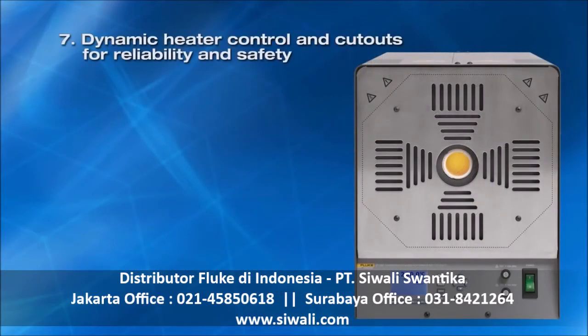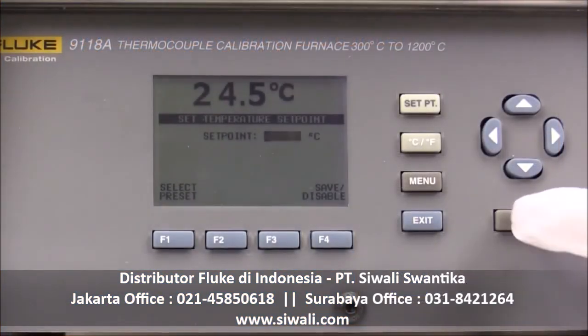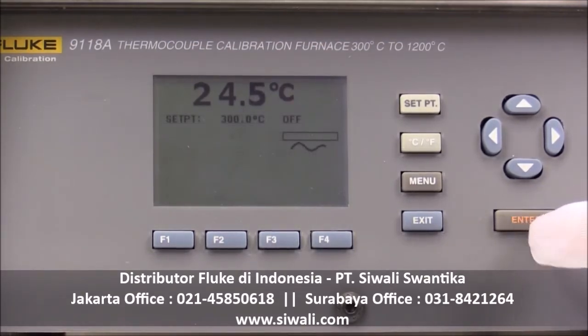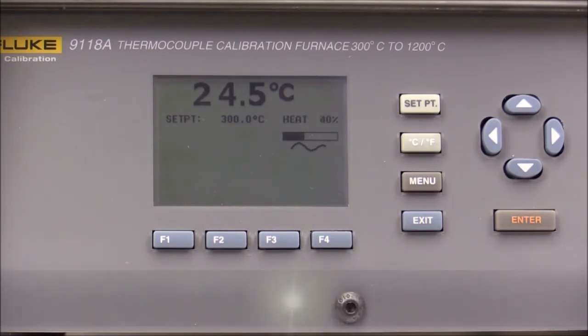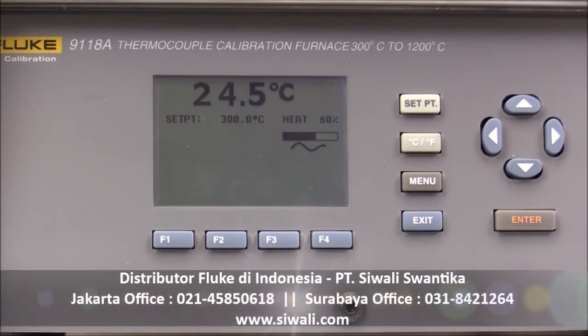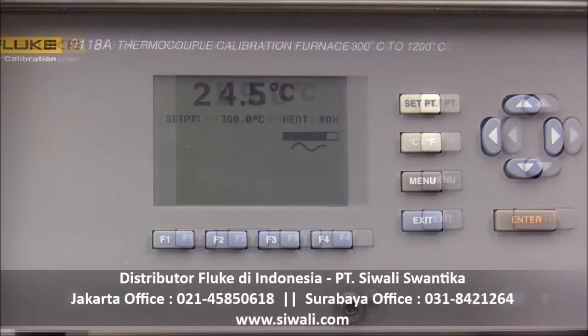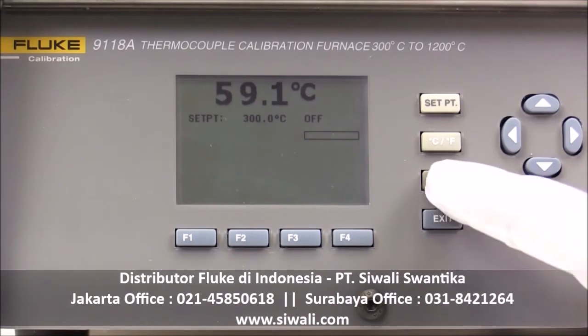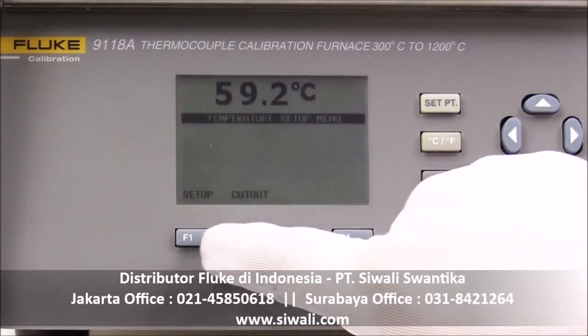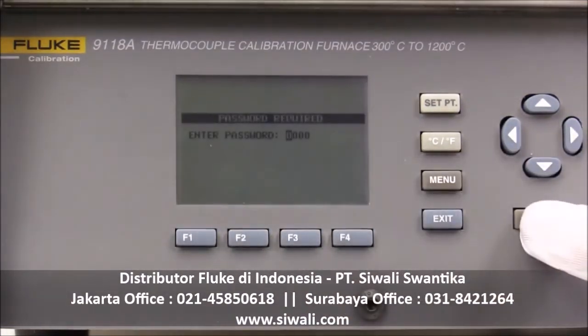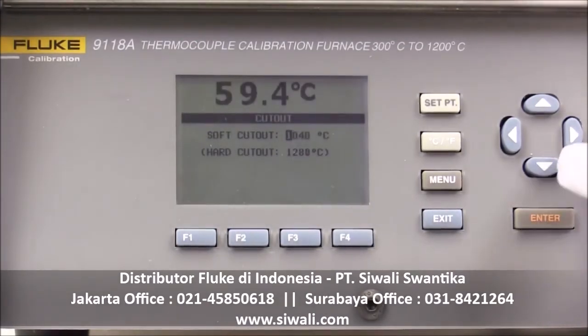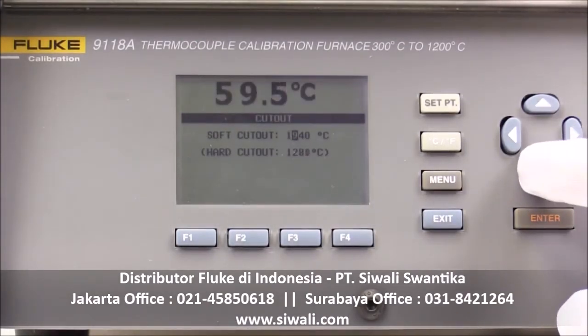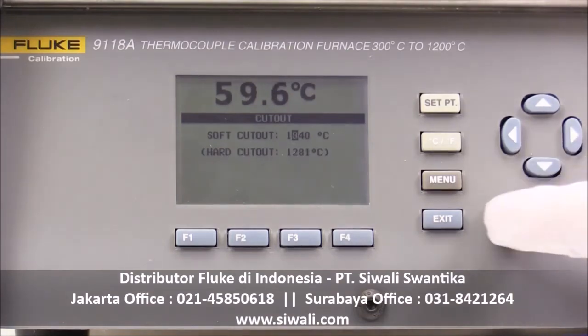And seventh, dynamic heater control and cutouts. Some furnaces include a spare set of heaters as part of the standard equipment, because heater failure is an all-too-common occurrence. The 9118A controls the heater power level below 100% to prevent the heater elements from overheating, improving heater reliability and extending lifetime. Redundant over-temperature cutouts are built into the 9118A to ensure safe operation of the furnace. These include over-temperature, chassis thermostat, fan fault, control thermocouple fault, and user-programmable cutouts.